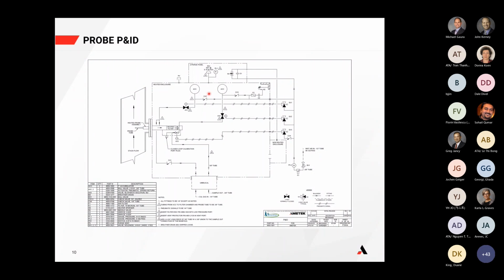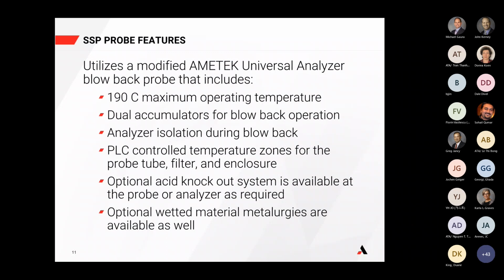There are two separate cycles. So as I said, we first blow back the heated filter, we then blow back the heated probe, and this cycle is repeated twice. Typically, the cycle takes about 2 seconds per cycle. And Michael will talk to some extent about how that works with the controller system. Sorry, I keep having to switch screens here to change slides.